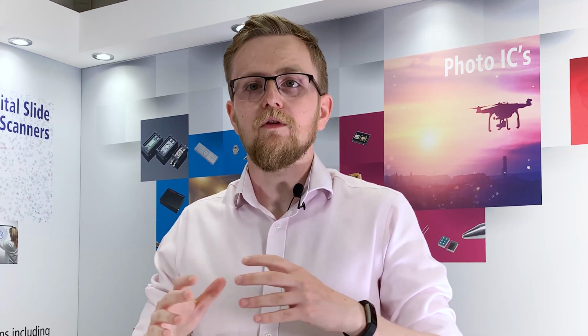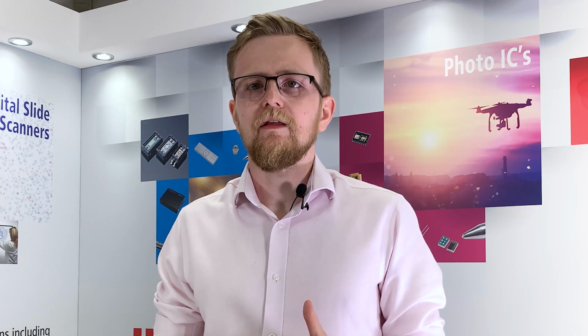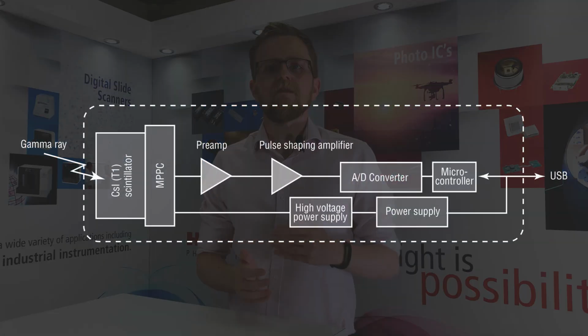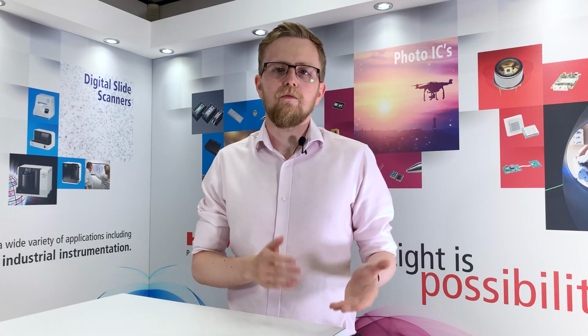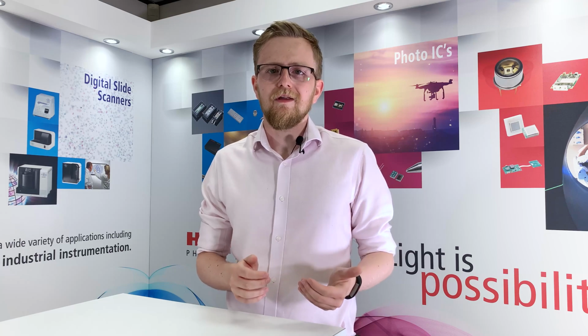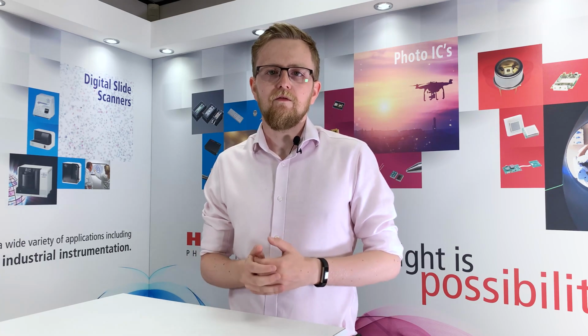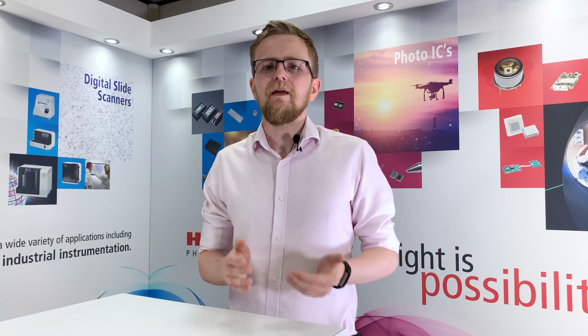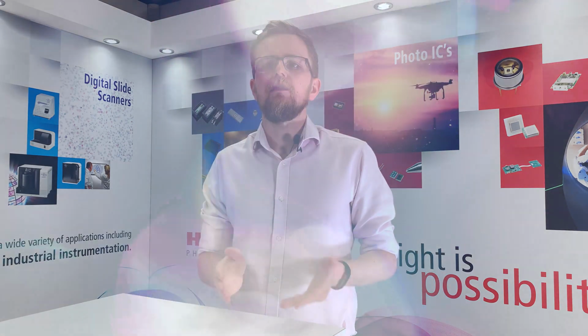Because we can't see the radiation being measured, we need to use how the radiation interacts with the surrounding environment. The main way of doing this is by using a scintillator over an optical detector. A scintillator is a material that when hit by ionizing radiation exhibits fluorescence or phosphorescence of visible light. This light is then captured by the detector for measurement. The scintillator is chosen based on the type of radiation that you're looking to measure, how energetic it is, the speed it decays, and the wavelength of light you need for your detector. The light collected from the scintillator at the detector can then be used to analyze the sample.